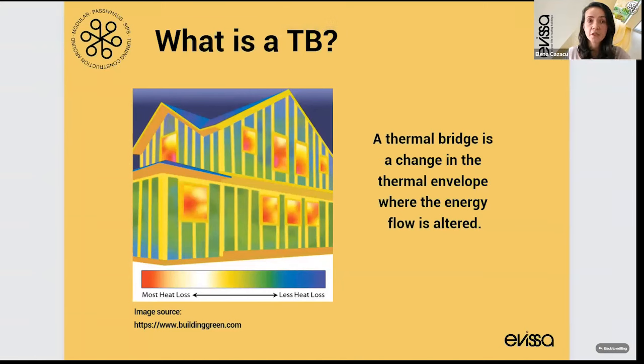That means that we've got insulation in the roof and the walls, and the owners have done a good job in insulating their walls and roofs. However, the timber stud frame or metal stud frame, actually I don't know exactly what that is, shows signs of greater conductivity. So they are essentially seen as thermal bridging. And windows, they aren't performing very well. Windows are probably the worst component of this building fabric. I'm not sure if that answers it, but simplistically, that's how we would navigate the thermal bridge image. Yeah, I think that's good.